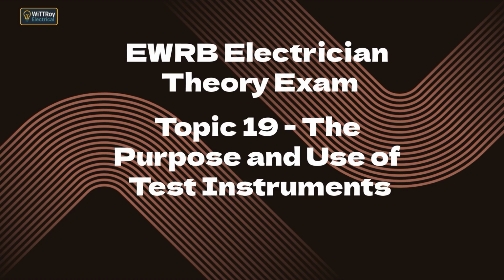Topic 19b. Explain how the above types of test instruments should be connected to test the circuit. Each instrument has a correct way to connect. Insulation resistance tester is connected with the circuit isolated and conductors separated. We test between active earth, active neutral and neutral earth.